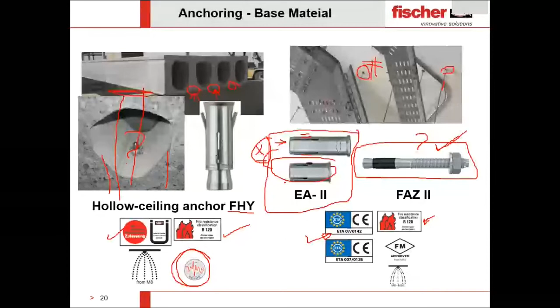Now, sometimes people use wedge anchors. In some projects, the specification requires only wedge anchors to be used. Why do consultants sometimes ask for wedge anchor? Actually, wedge anchor is safer, but it's difficult to install with a threaded rod—you need couplers or a bracket or something. But also, wedge anchor is approved for seismic load, meaning earthquake force, while drop-in anchor cannot be approved for seismic force. We will see this in the next slides.